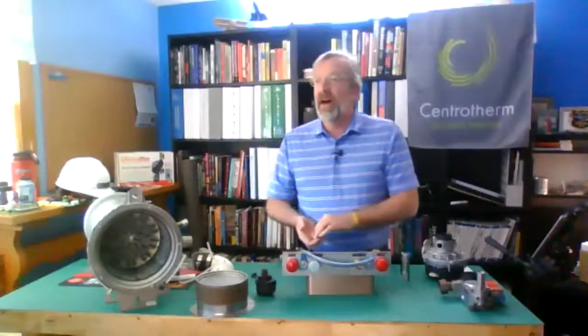What we'll do for Friday is we're going to kind of pre-disassemble. We're going to take all the nuts and bolts off of one. We'll show you everything whole on one of the boilers, and then we're actually going to pull the parts apart while you guys watch, but just so you're not looking at my backside while I'm taking out nuts and bolts, because that can get tiring pretty quick. We're going to go over how to flush and rinse out the heat exchanger. We're going to discuss cleaning the burner. We're going to put it back together. We're going to pressure test it, and then we're going to do a combustion analysis. And I'll probably adjust it just because you guys are watching. So that'll be on Friday if you want to jump back. It could be entertaining. I'm making my son do it, so we'll see how that goes.